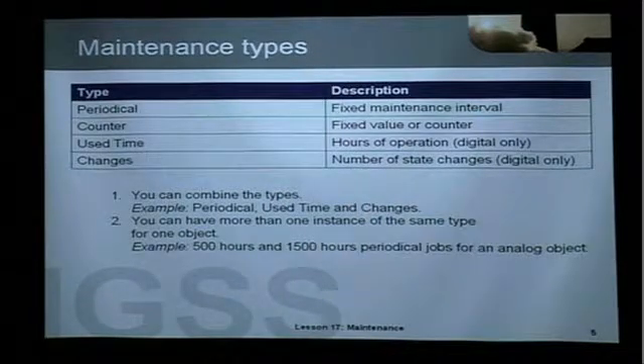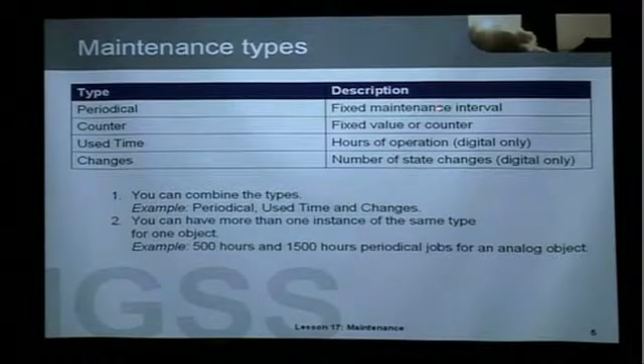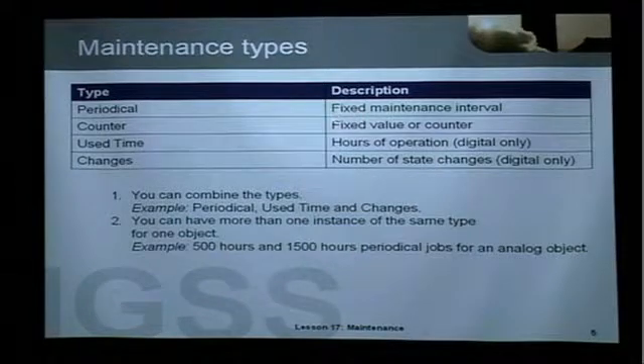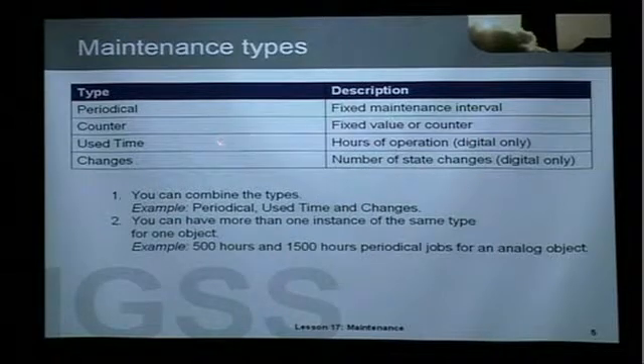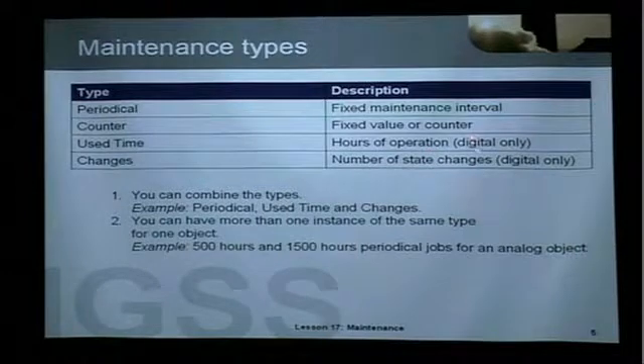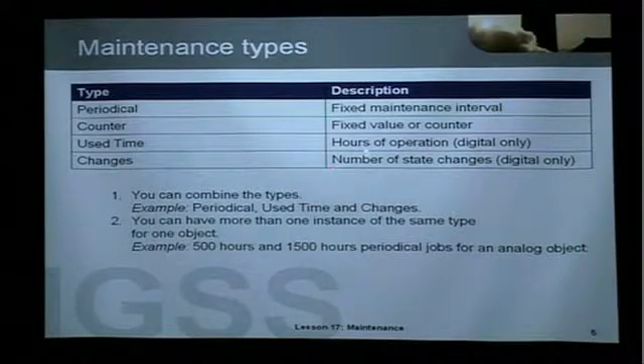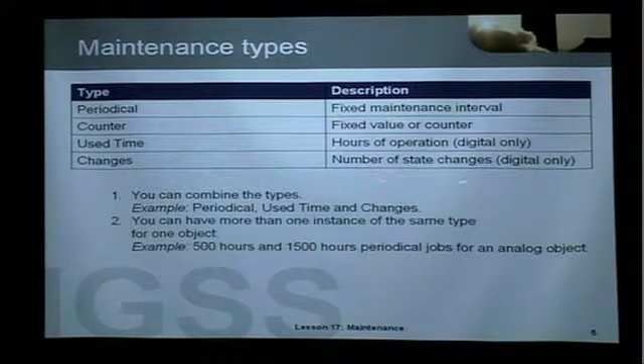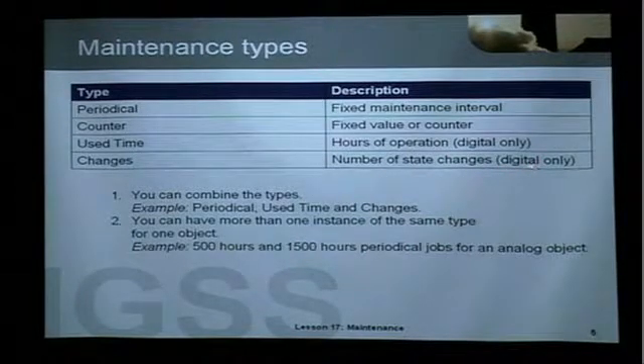We have four different maintenance types in IGSS. We have periodical maintenance, which is a fixed maintenance interval. We have counter maintenance, which is due when a fixed value or counter is exceeded. We have use time, which means hours of operation of a motor or pump, for example — for digital objects only. And we have changes, which means that you will have maintenance after a specific number of state changes of your pump or motor, for example. This is also only applicable to digital objects.